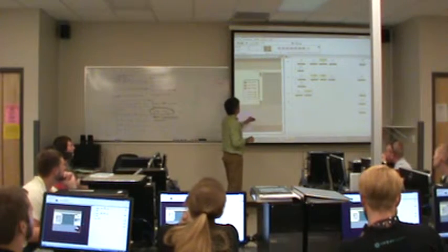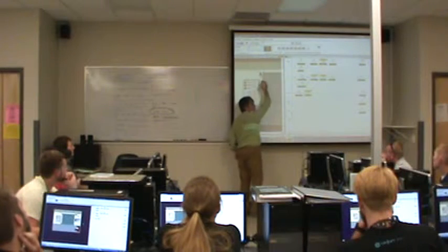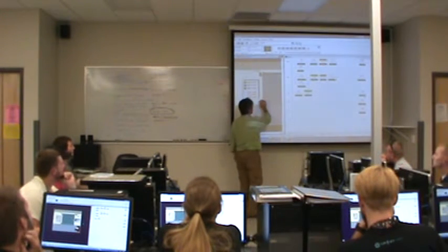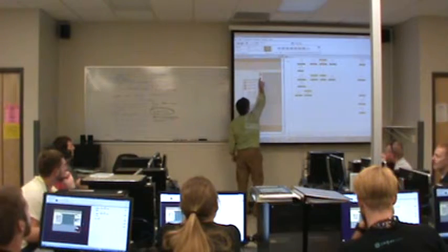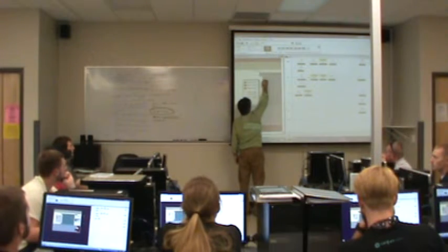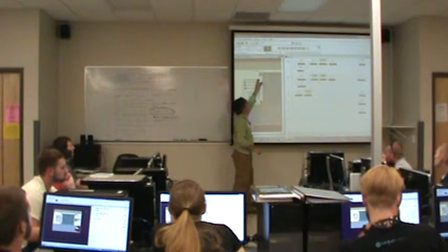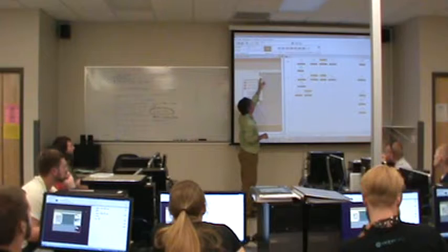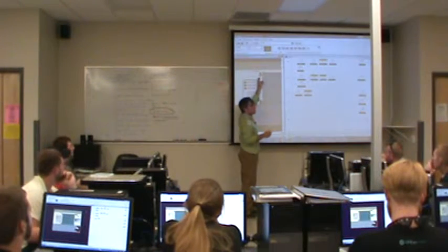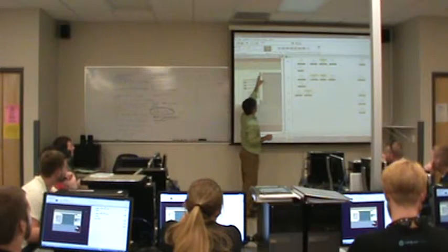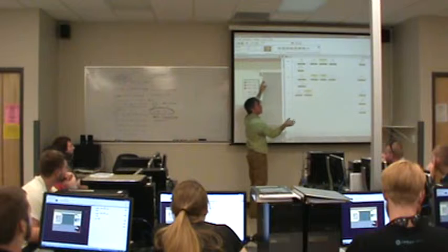Okay. I think the open lamp should be on when the door is all the way open. So it's not just the lower limit switch I care about, it's more the upper limit switch that I care about. So when this upper limit switch is not passing power, the door is all the way open. Okay? So let me use the upper limit switch as a condition. I think that's what you meant. When the switch is not passing power, that means it's in its normal state, and so I want to invert it. So I'll take an inverse set of contacts, and I can never remember which one's examine open and examine closed.